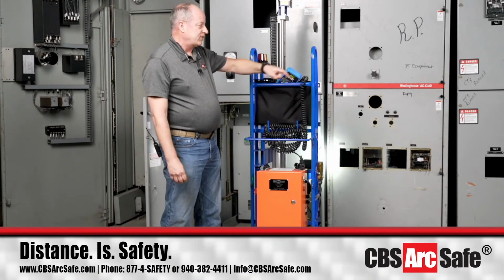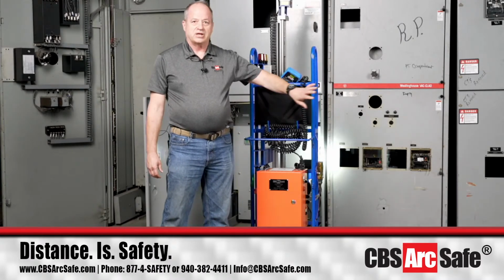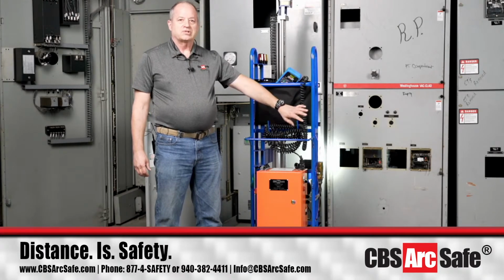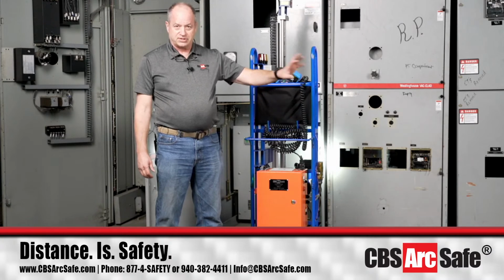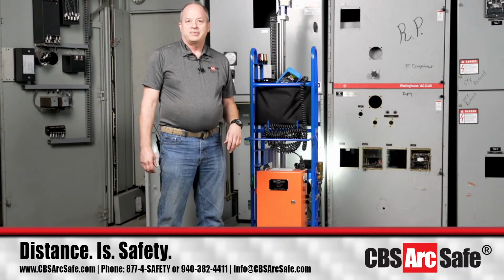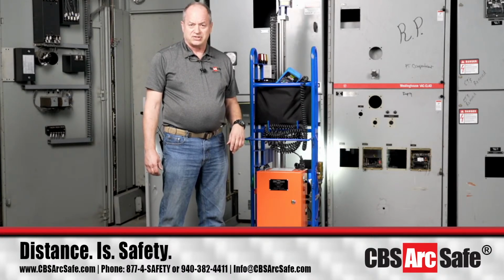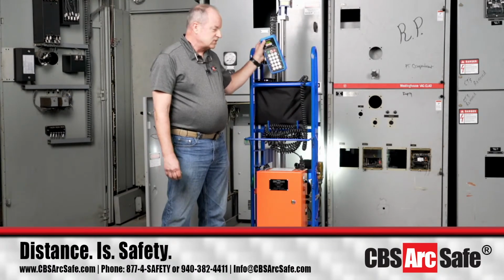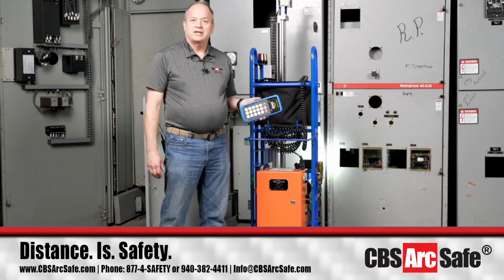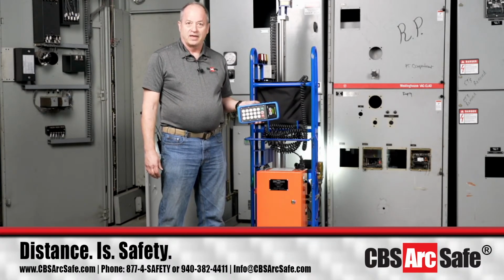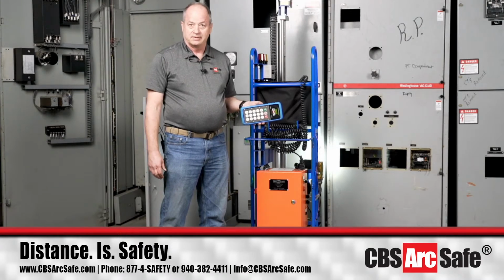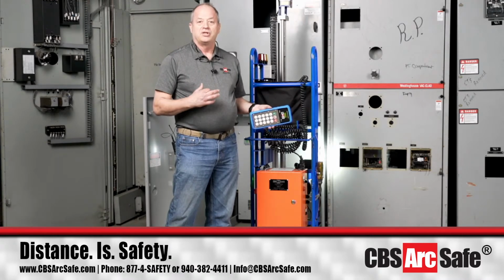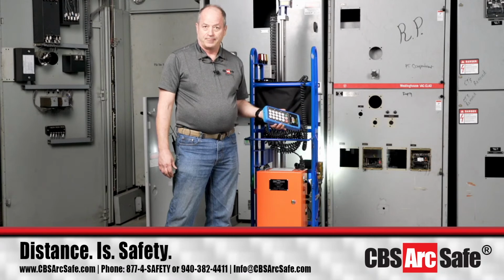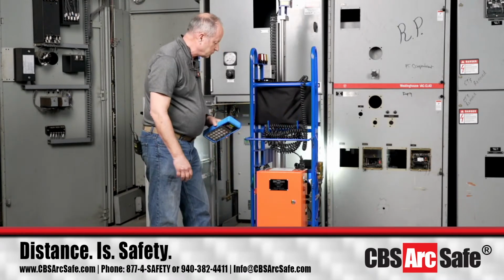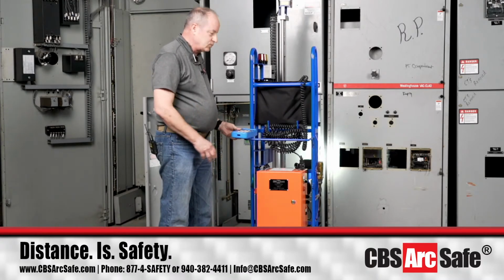Well, if you've got a large arc flash hazard boundary where you can't stand in the substation, and I've been in a cement plant, I won't say what company, but down in Midlothian, Texas, so that gives you 3 companies there. Their VCP-W had a 294-foot arc flash hazard boundary on the switchgear. With the radio remote system, we can get out to 100 meters. So we sat out in the parking lot under the live oak tree and watched the RRS-1 rack the breaker in and out safely outside the arc flash hazard boundary. So if you have high arc flash hazard numbers and you need the radio remote and the video monitor, we have that capability. While we're not showing it to you today, understand that we can easily do that.